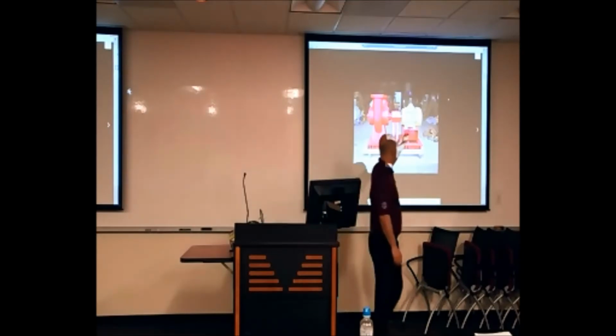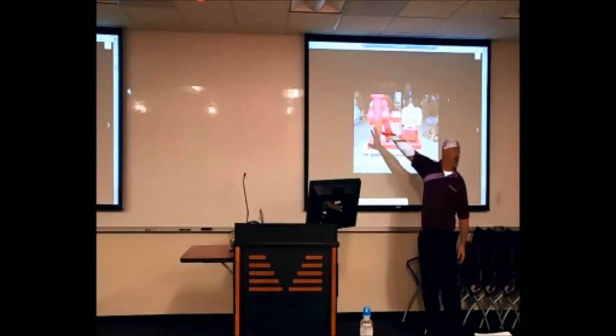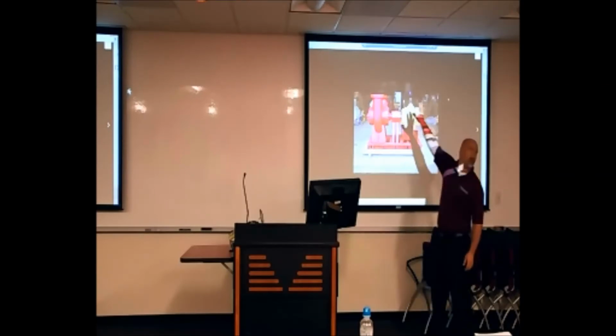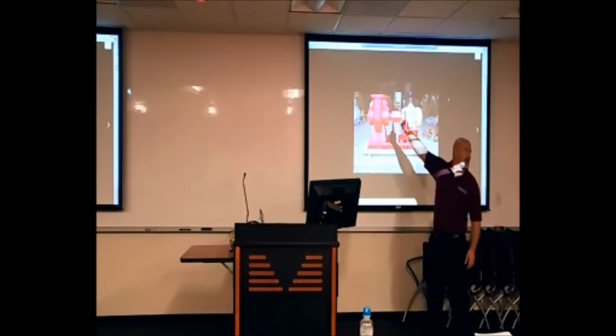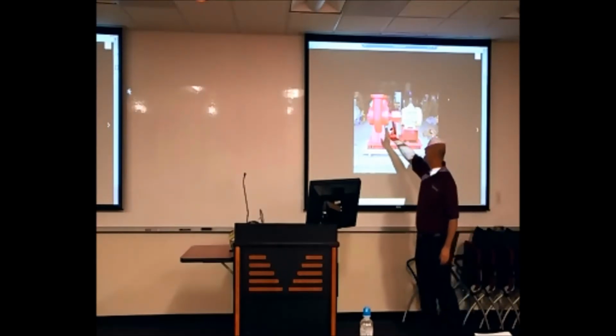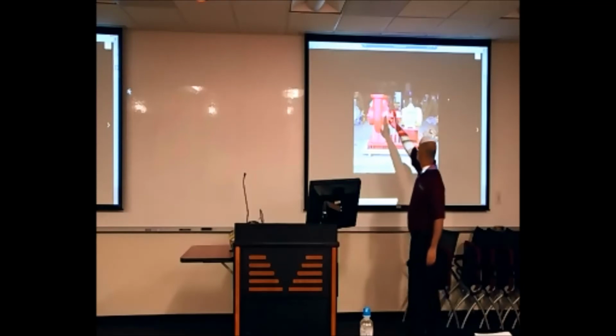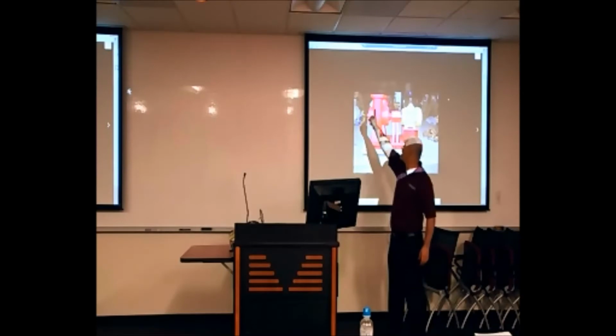Right here on our picture, I'm just going to use this one picture because it's very simple and showing what's on the pump from basically left to right. Starting with the left side of the pump in the red is the actual pump portion of this. On the right side is the motor portion of it in gold. Between the two, we have a coupler that connects the two together. That is a rubber style coupler that allows some flexibility in there. And then working our way from the pump across here, we have mechanicals that we need to identify. We have our bearings and seals on each side of the pump, the bearing and the seal inside of there.